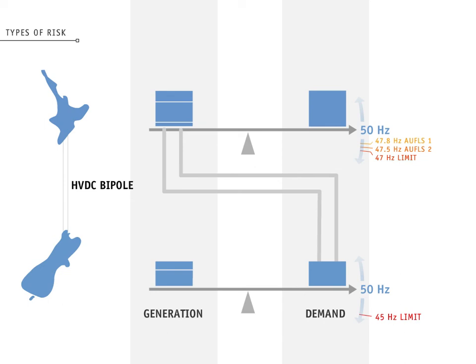Both islands are now back in balance. Under a high North HVDC transfer scenario, if the bipole trips, up to 32% of the North Island load may be disconnected due to the operation of AUFLS. A four to six hour process of redistributing generation and restoring the shed AUFLS and interruptible loads will be required to get things back to normal.